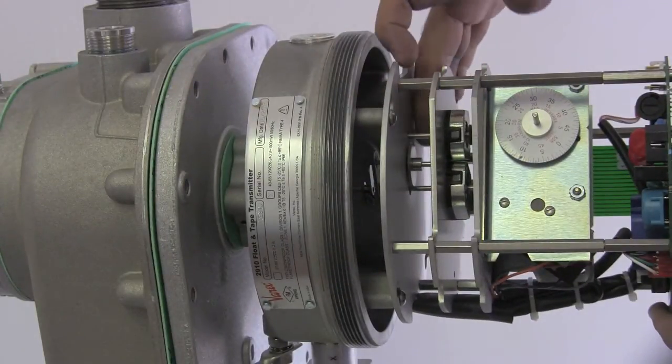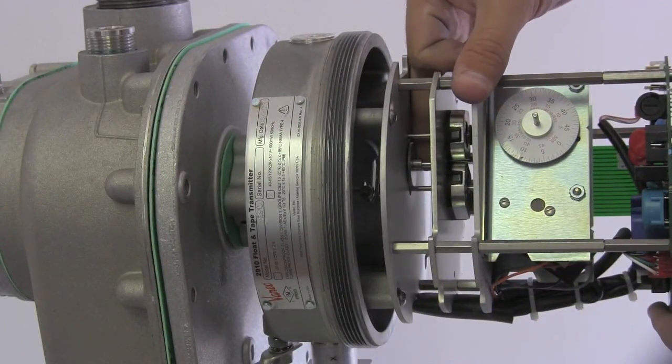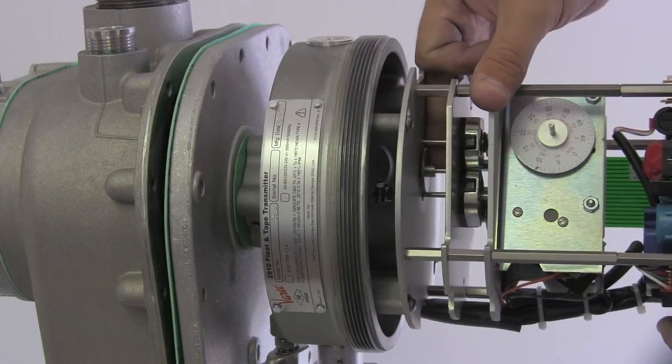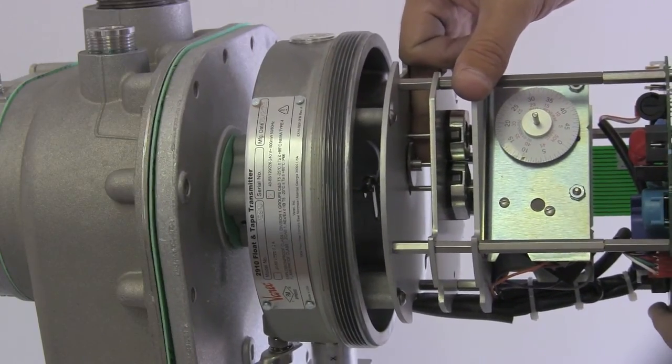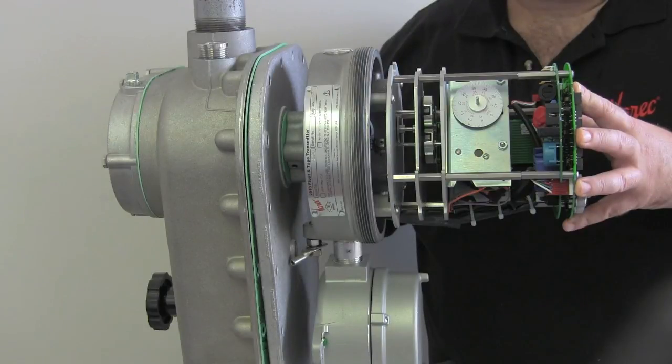Now turn the transmitter shaft so that the coupling bumps against the sprocket pin. Pull the gauge cover back slightly, enough so that you can turn the coupling just enough to engage onto the pin. And check to see if the pin and coupling are engaged.